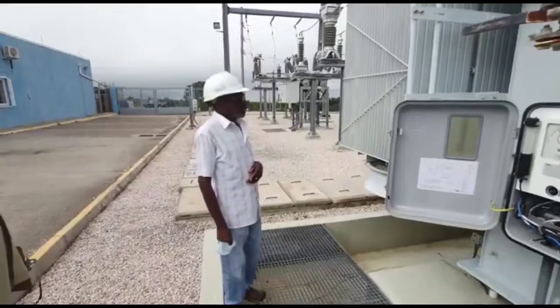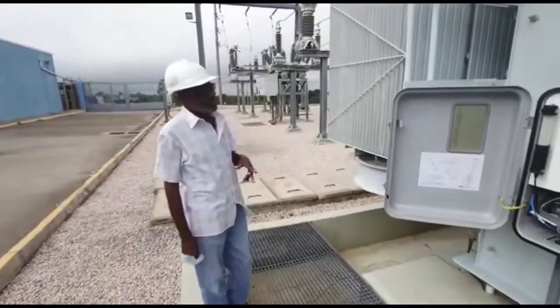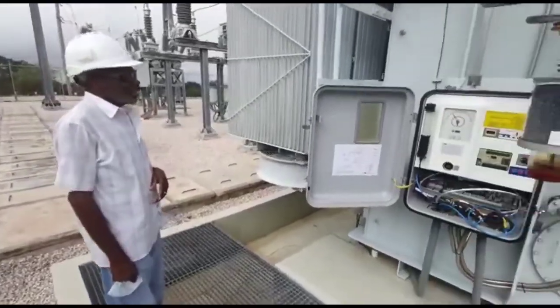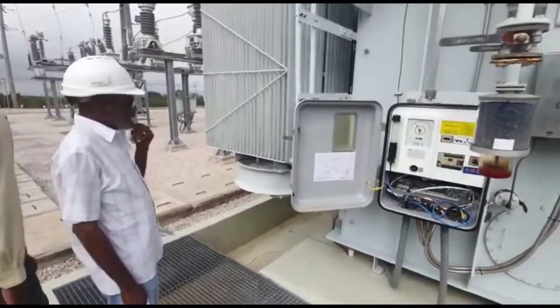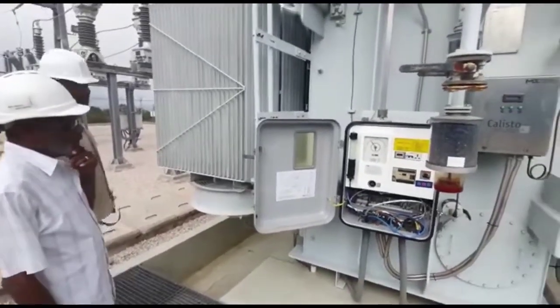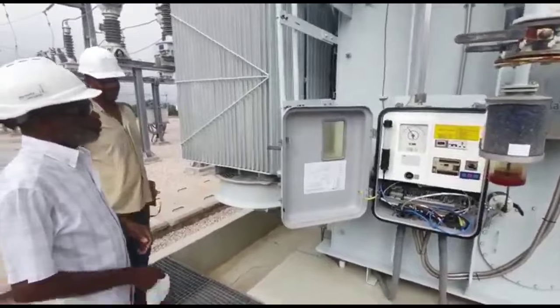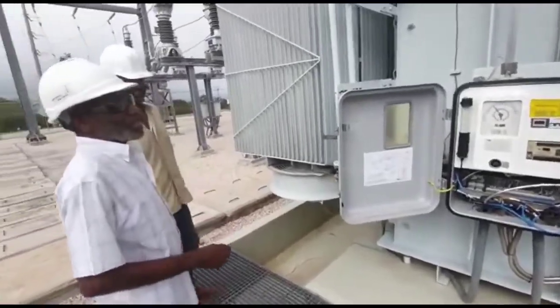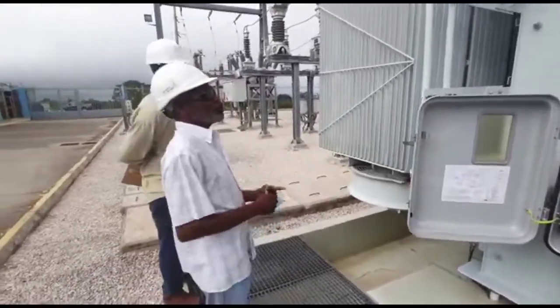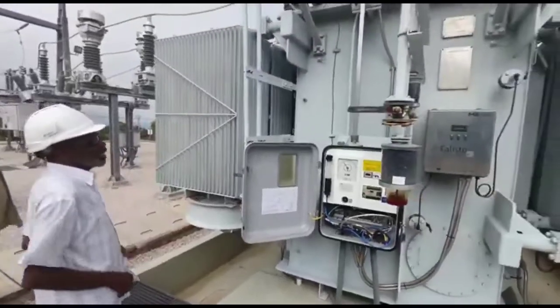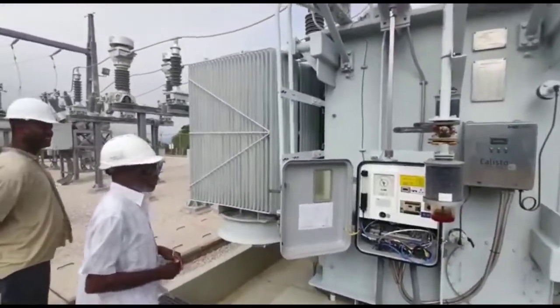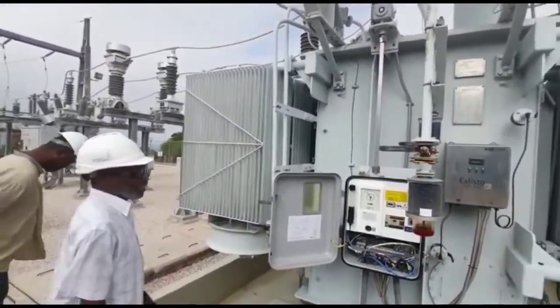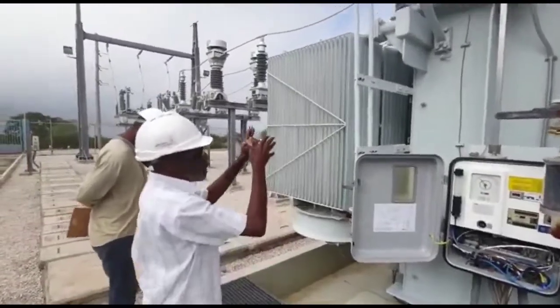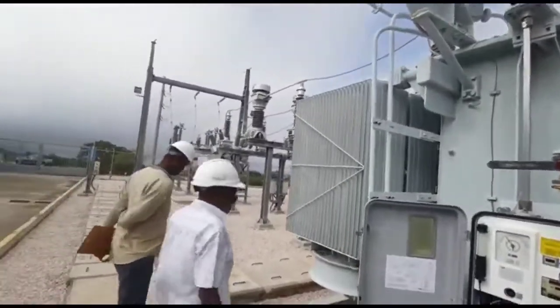Okay, Joel had explained what the transformer is and how it works, and I'm going to try my best to repeat what he shared and see how much I've learned from him. The transformer consists of two sides, the low side and the high side. The low side comes in at 34.5 kV. The high side of the transformer is 69.5 kV, 69 kV.